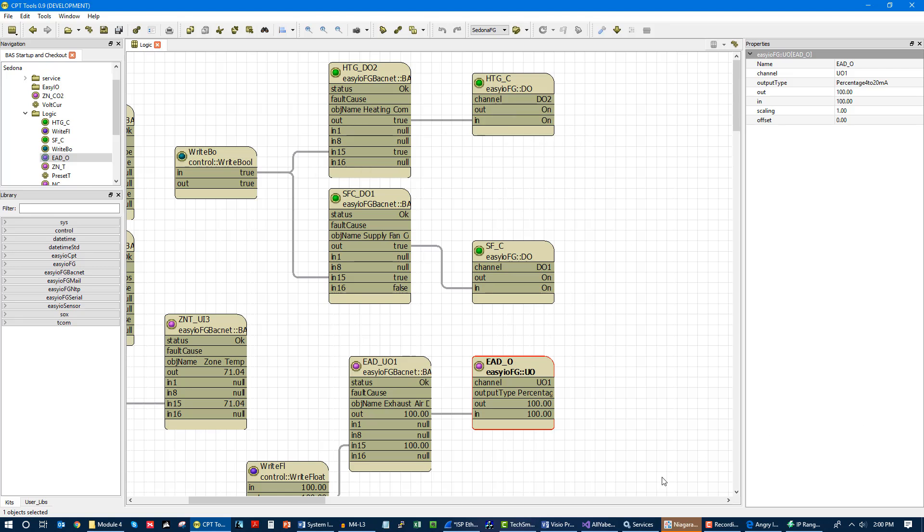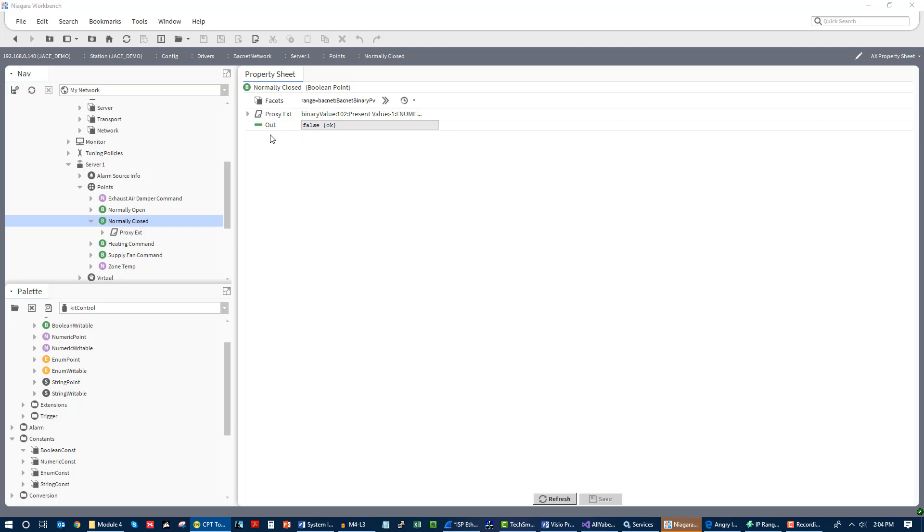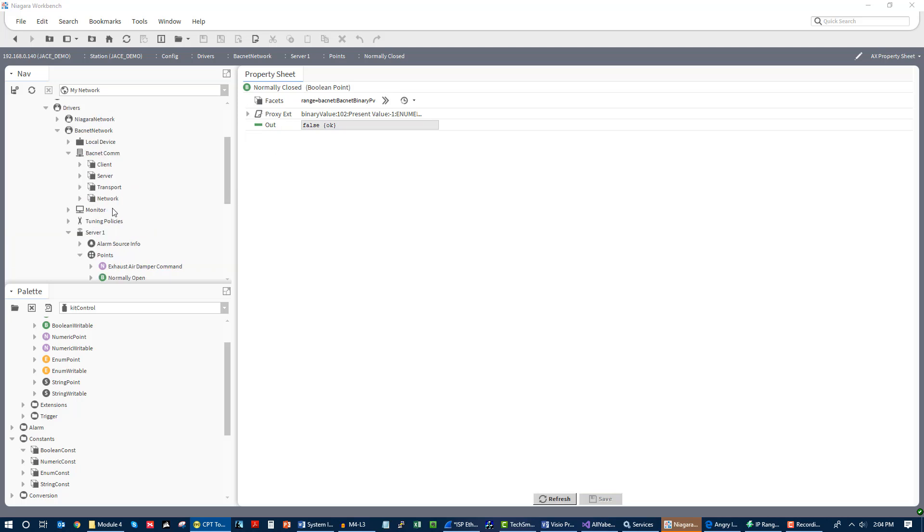I'm going to go back here and we're actually going to watch the state change as I change the output at the controller. You see it changed to true and now I'm going to change it at the controller again and it should change back to false. What we're actually seeing here, we saw the physical point in the controller and you might have heard the relay click in the background, but we're actually seeing the BACnet logical point change state. This controller is actually interfaced via field trunk, which we'll talk about in the next BAM TV episode, but we see it actually going and changing state. And so that is the difference between a physical point and a logical point.